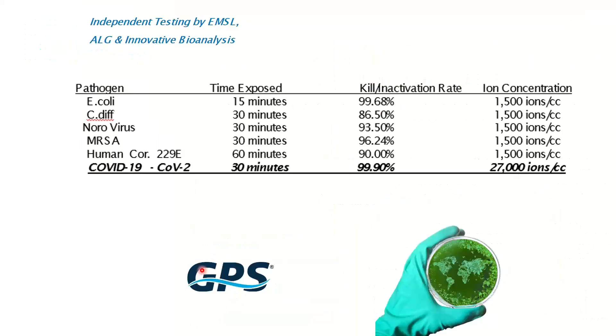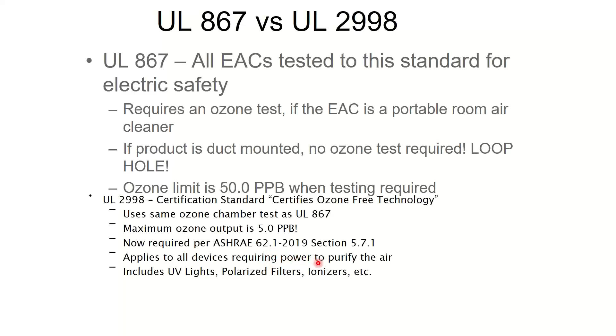I mentioned UL 2998. That's the new certification available for air cleaners to verify that they don't have any ozone production — actually, to verify they have 5 parts per billion or less, which is a pretty small number. There could still be a little teeny tiny bit, but way less than any other electronics in your life produce, so basically it's statistically zero. That's required by ASHRAE 62.1 2019, like I mentioned. Coming soon to a mechanical code near you.